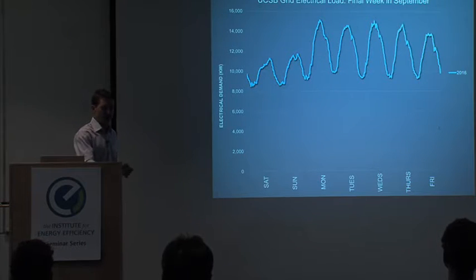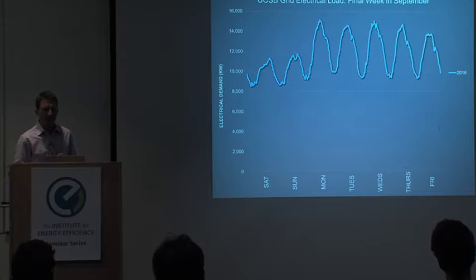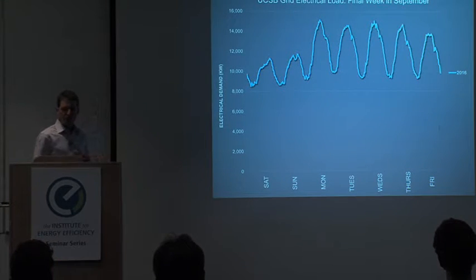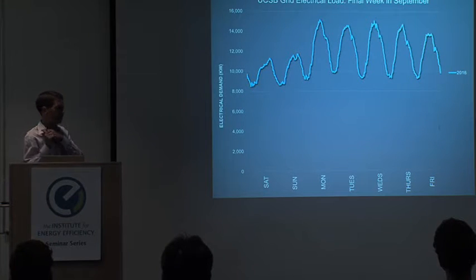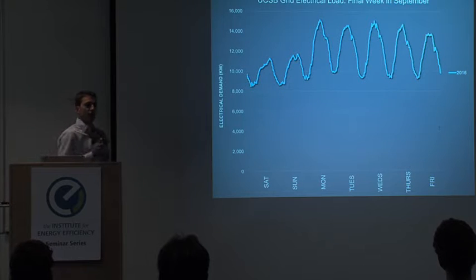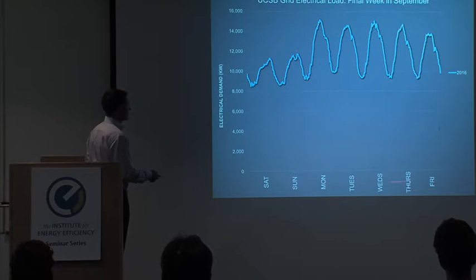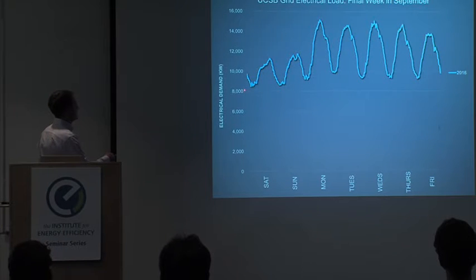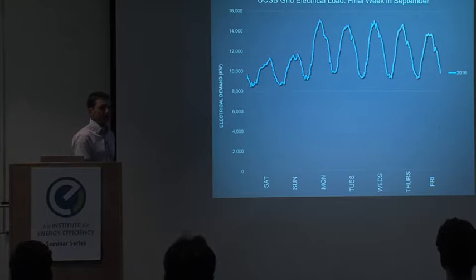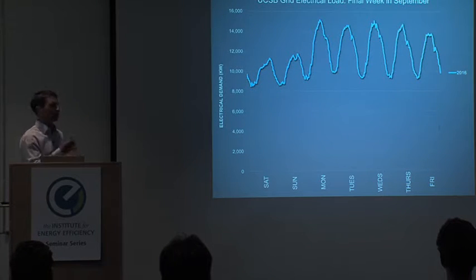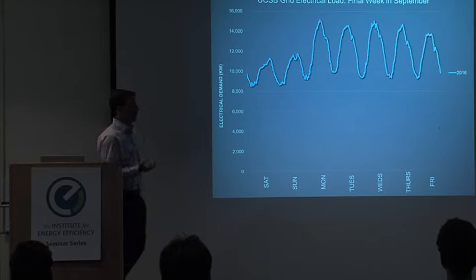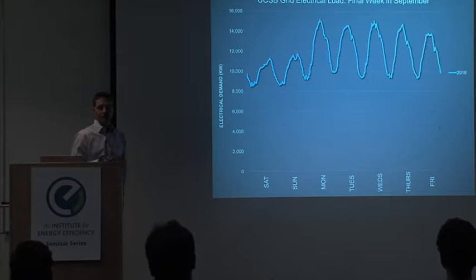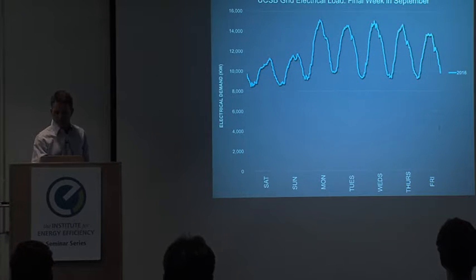So what's this doing to our electrical load? This is a week of power demand data for the 66 kV substation. We have one meter that serves the whole campus at that substation, and this is Saturday through Friday, 7 days, you can see the weekend. We're anywhere from 8 megawatts plus to 11 megawatts, and during the week we peak at about 15. It's pretty typical, predictable load. I chose this week because it's really the first week classes are back in session, typically pretty hot, and the campus is at its highest use and demand levels. So that's what our load looked like in 2016.